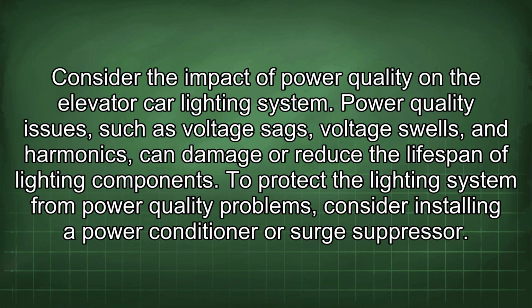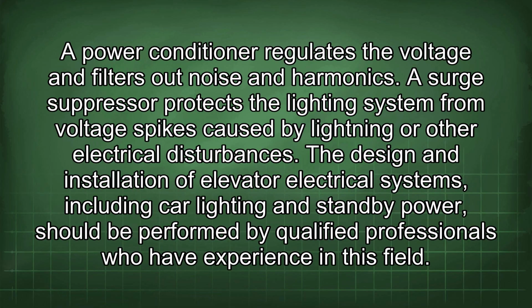Consider the impact of power quality on the elevator car lighting system. Power quality issues such as voltage sags, voltage swells, and harmonics can damage or reduce the lifespan of lighting components. To protect the lighting system from power quality problems, consider installing a power conditioner or surge suppressor. A power conditioner regulates the voltage and filters out noise and harmonics. A surge suppressor protects the lighting system from voltage spikes caused by lightning or other electrical disturbances.